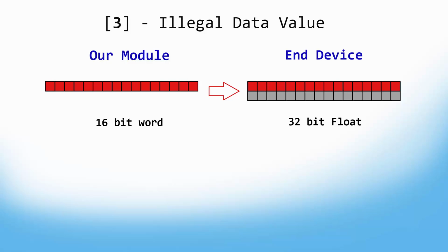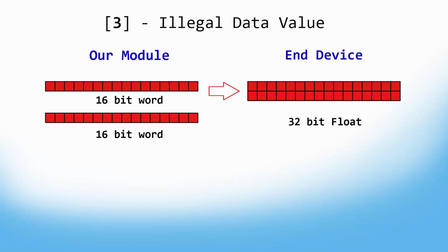In this instance, you would first need to check that you are writing to the proper address in the device, and then make sure that you are writing the correct data type. In the example, this would mean writing 2 16-bit registers to encompass the one float value.